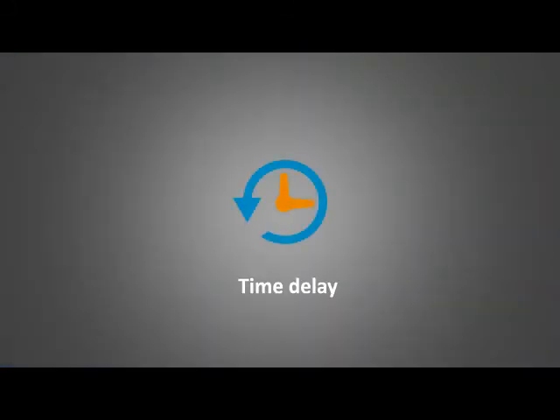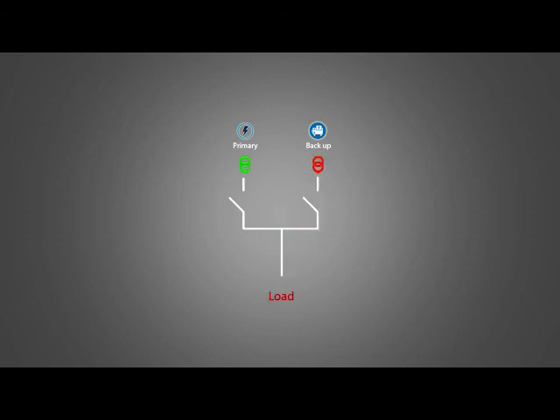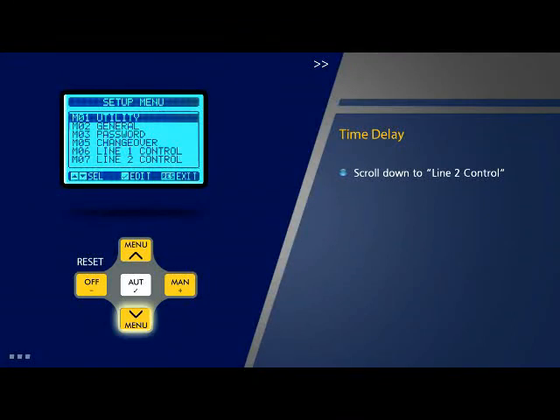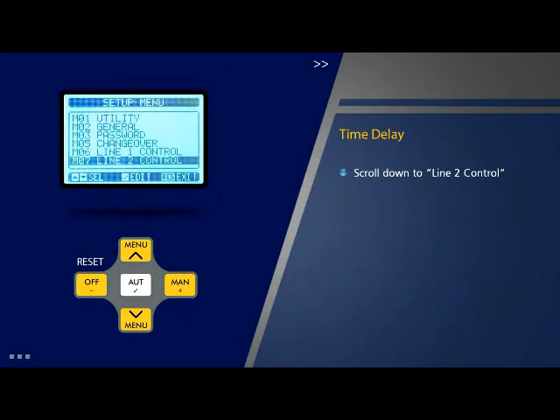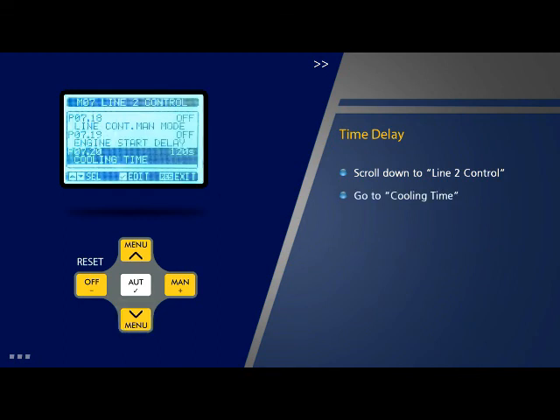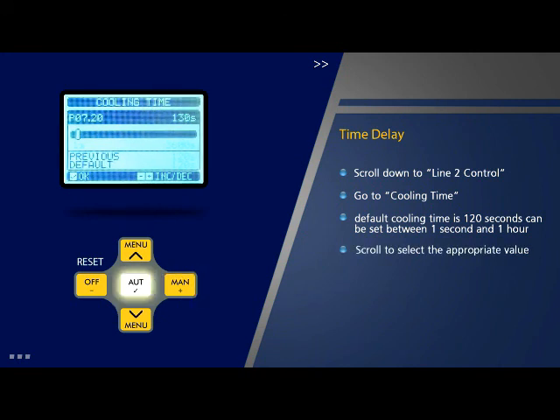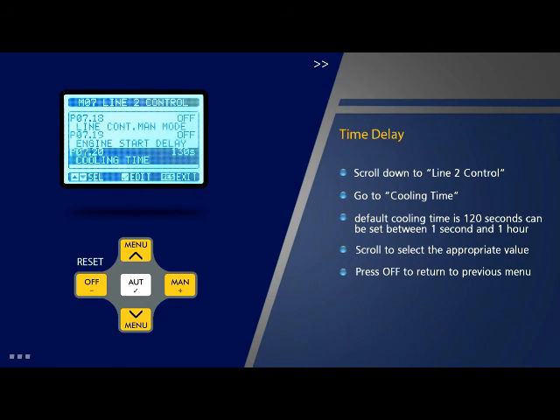Time delay — generator cooling time: Let us look at the procedure for setting the generator cooling time delay. It is the time delay between the load disconnecting from the generator and the generator engine actually stopping. Scroll down to 'Line 2 Control' on the setup menu page and press OK. Go to parameter 20 which is 'Cooling Time' on this page and press OK. The default cooling time is 120 seconds and can be set between 1 second and 1 hour. Scroll to select the appropriate value and press OK. Press off to return to the previous menu.